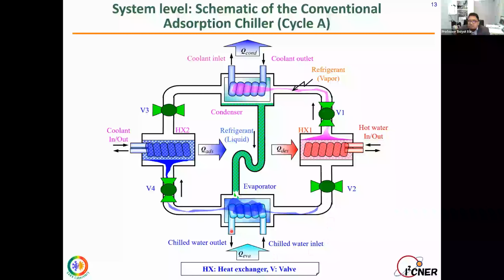The system is under vacuum, so the pressure is 1/100th of atmospheric pressure, about 1 kilopascal. At this pressure, water evaporates and goes through valve 4 to our adsorber bed, and adsorption happens here. Due to the exothermic properties of adsorbent materials, heat is generated in this bed, and we need to cool down the bed. On the other hand, here you can see valve 2 is closed. Instead of cooling water here, we are using hot water. This is our heat source. We can take this heat from solar energy or from waste heat sources, at about 80 degrees centigrade. And then we regenerate the water inside the heat exchanger.